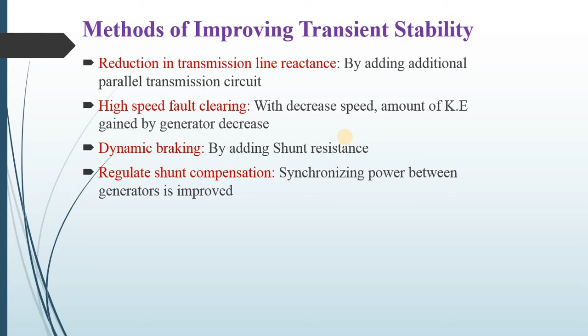Next is regulated shunt compensation. By maintaining system voltage around the power system, the flow of synchronizing power between the generators is improved. So we have to maintain shunt compensation to improve the transient stability of the system. Next is reactor switching. The initial voltage of the generator and therefore stability can be increased by connecting a shunt reactor to the system.